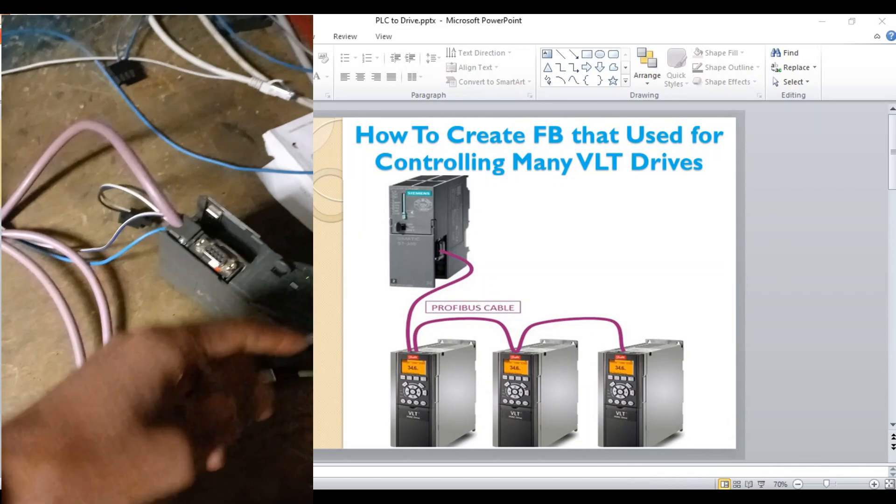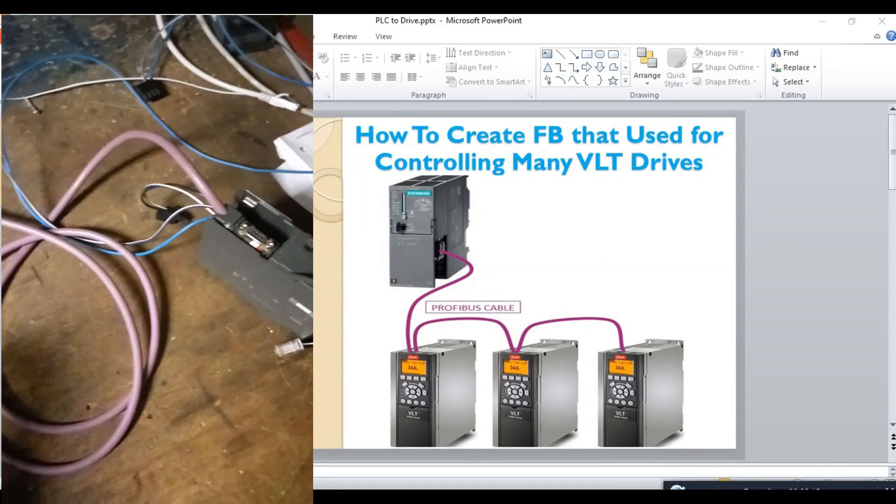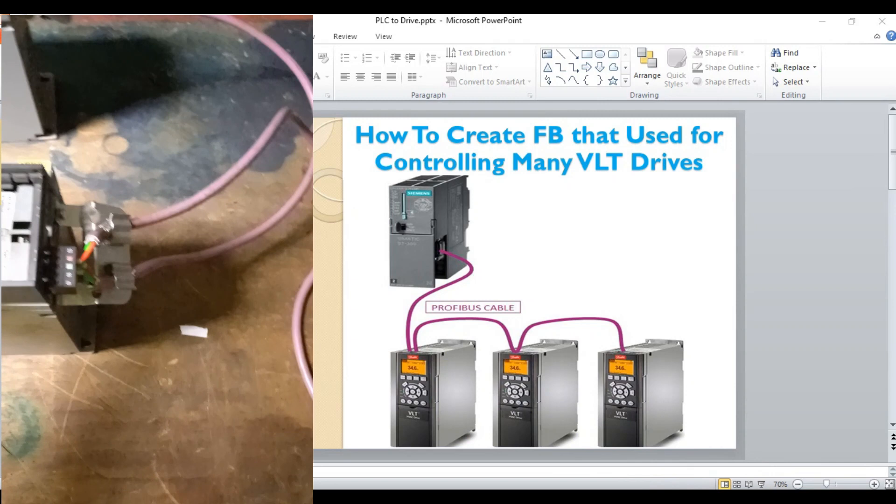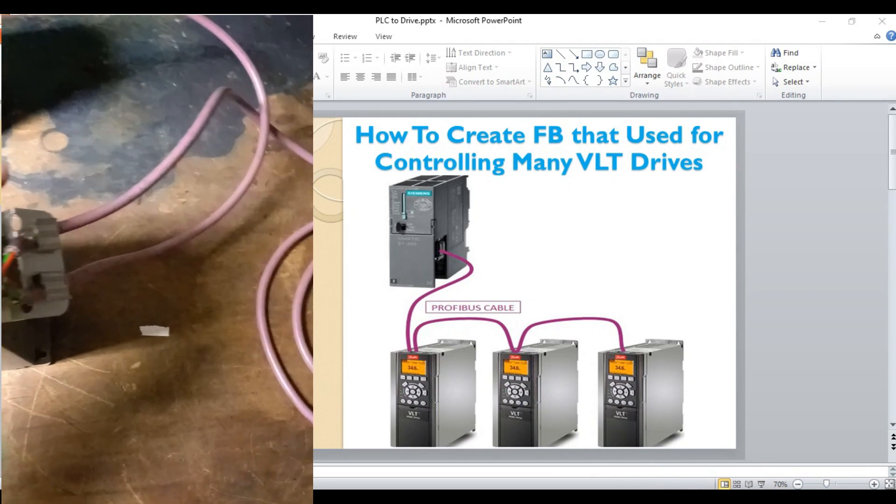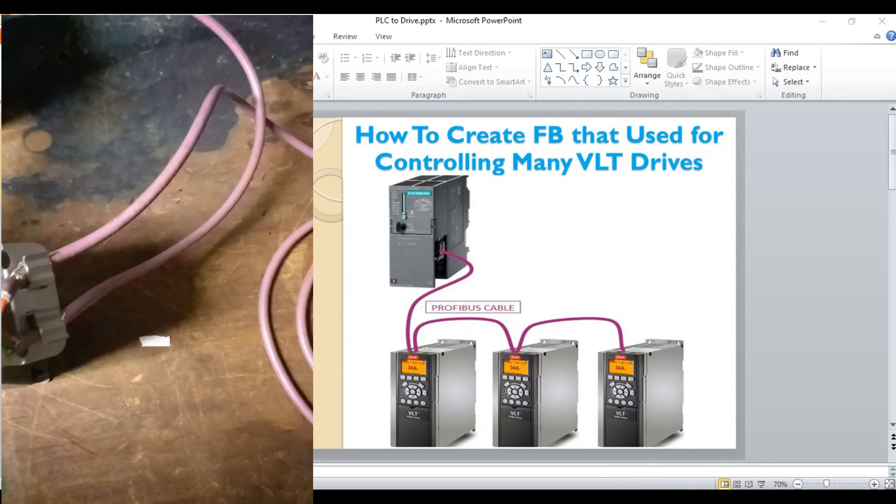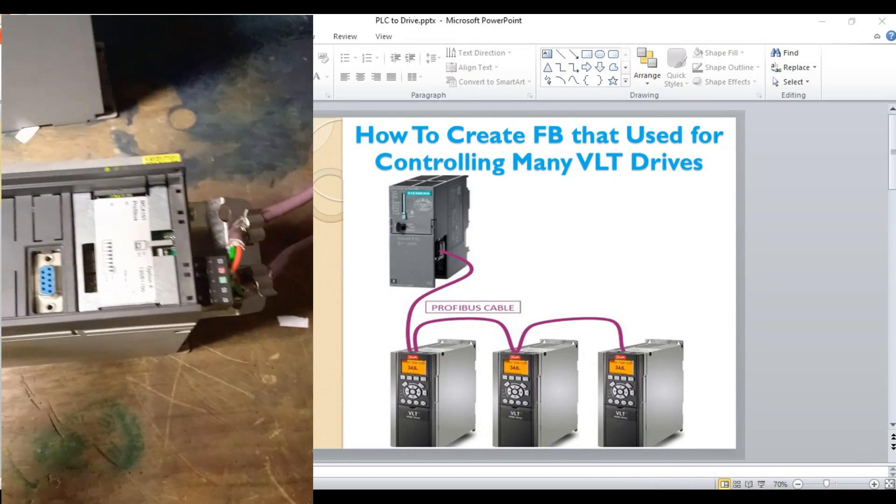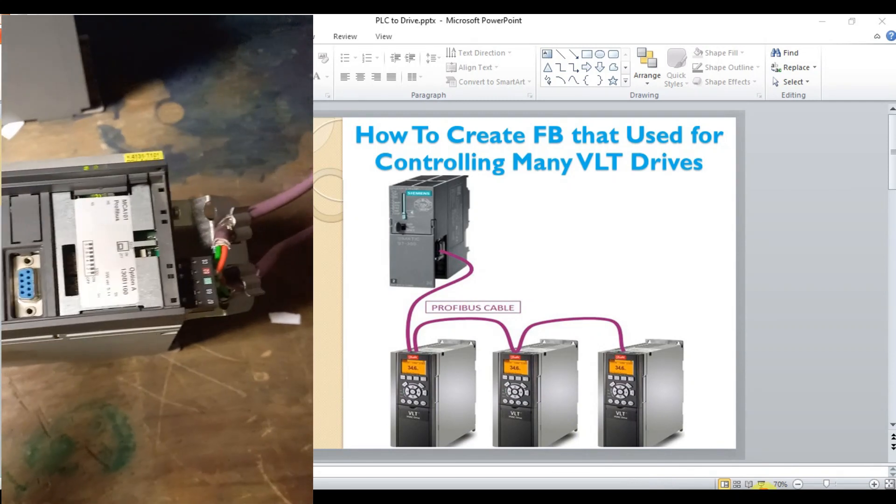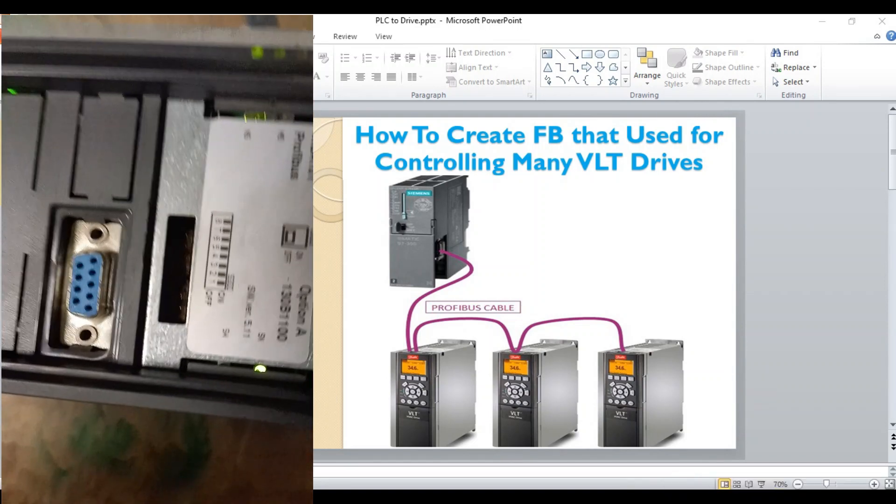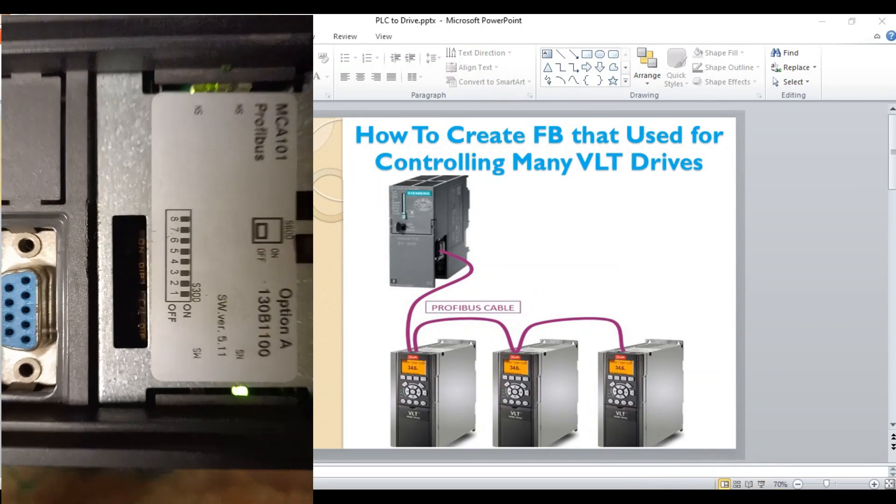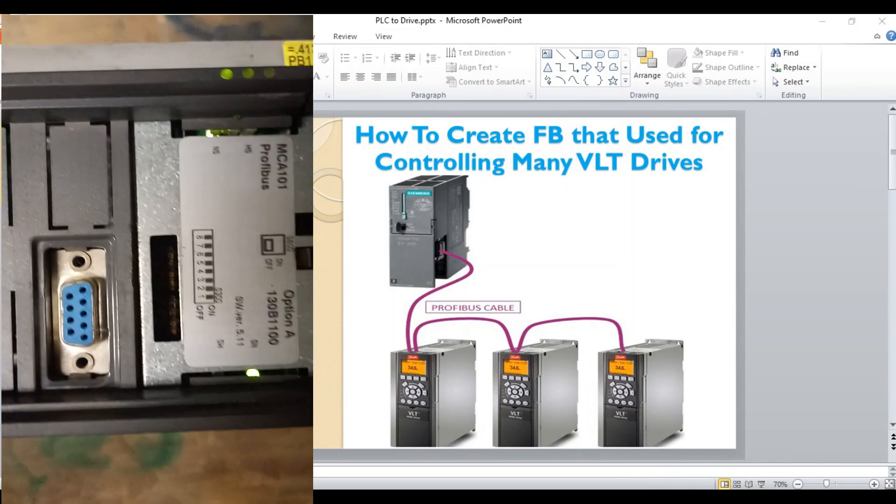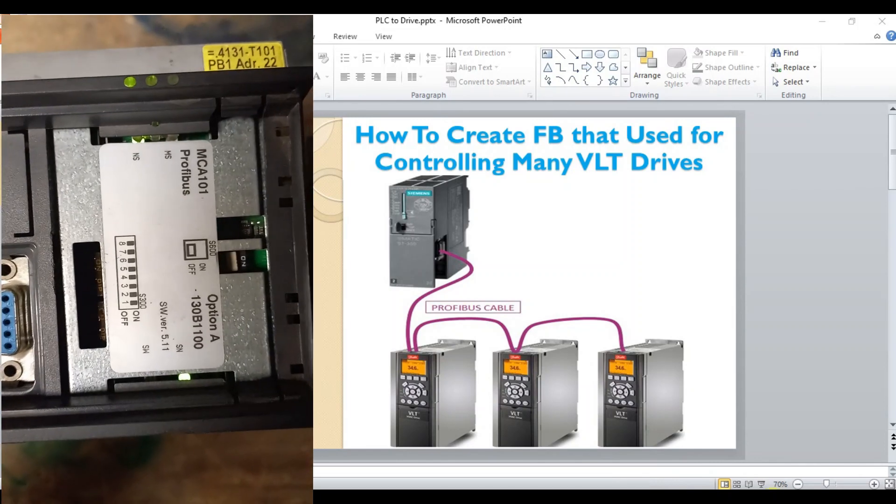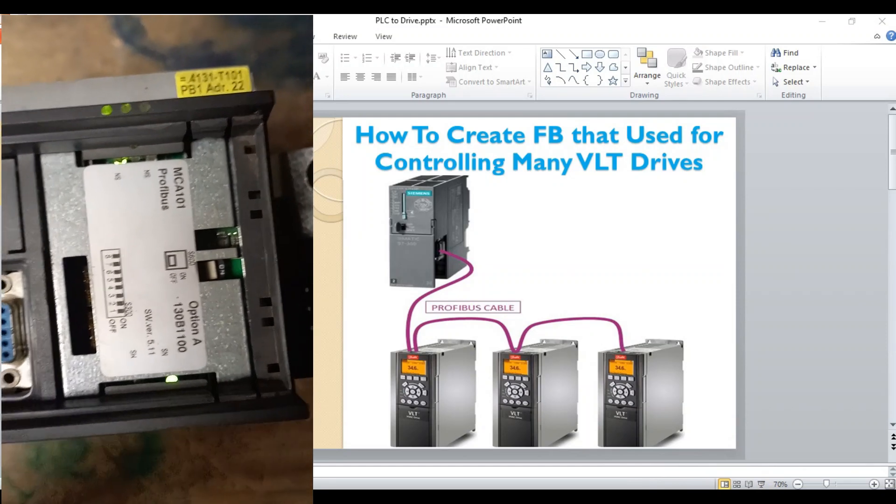The Profibus that comes from the CPU goes to VLT drive 1 then goes to VLT drive 2. The address of the VLT drive is assigned by DIP switches, as you see here. This will be set to 10 by switching the DIP switches.